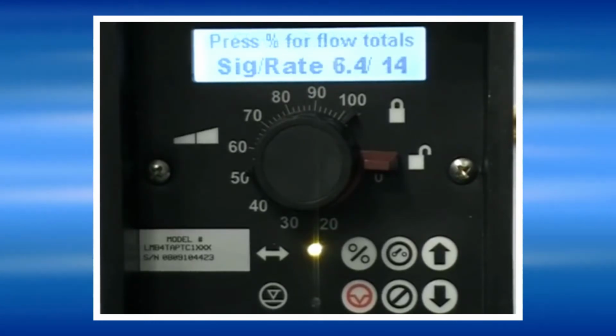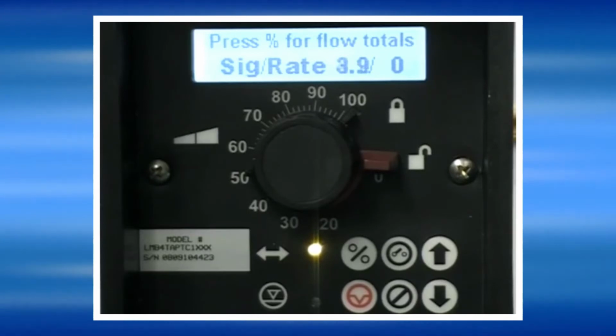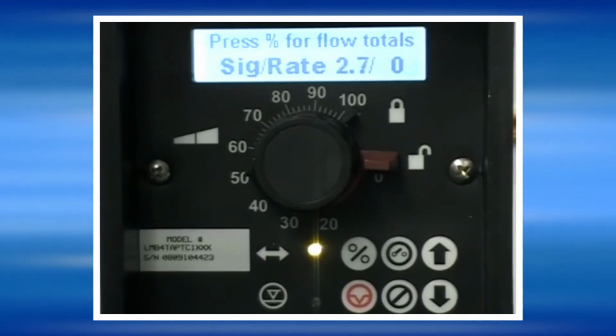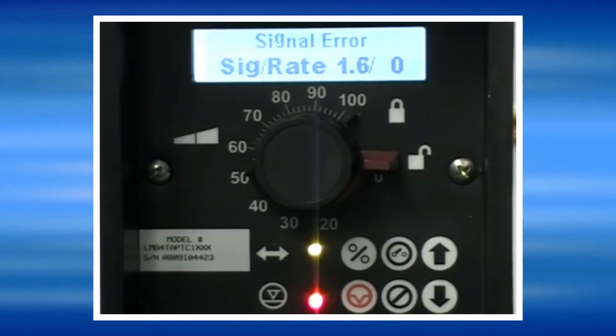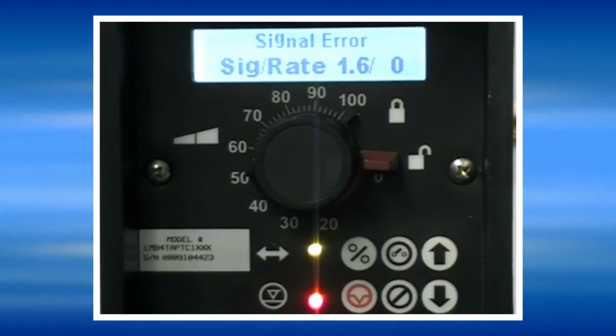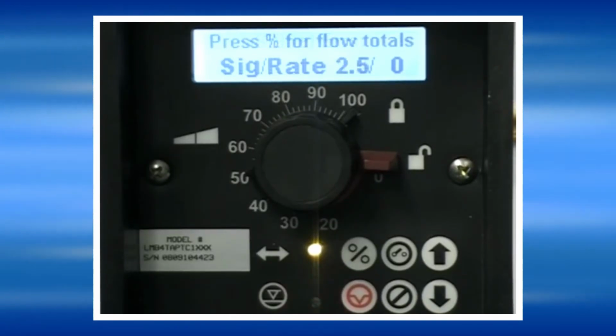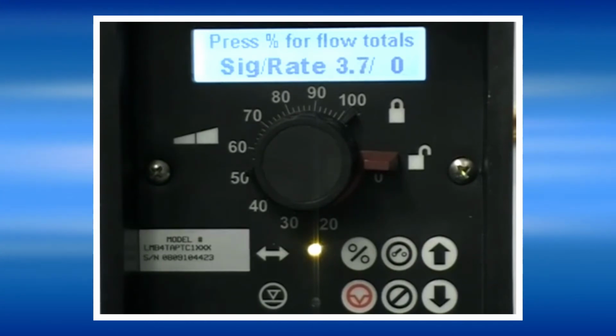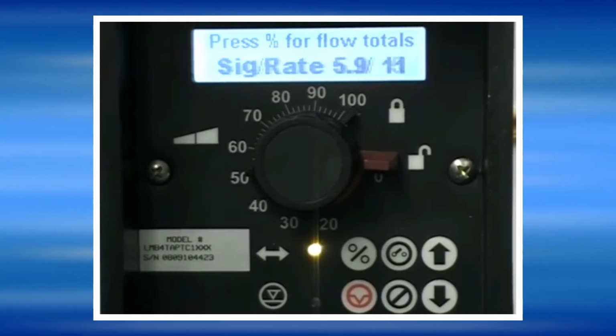If the signal, for some reason, drops below 3.8 milliamps for an extended period of time, the pump will go into a signal error message, which indicates that the unit has lost the signal from the sending device, or there may be something wrong with the cable. When the current signal is restored back to a normal reading, the pump will come out of that alarm and resume normal operation.